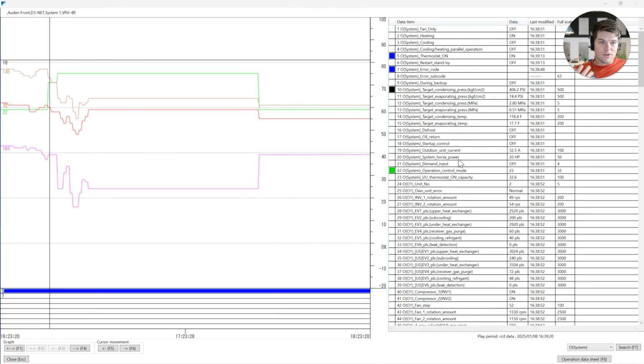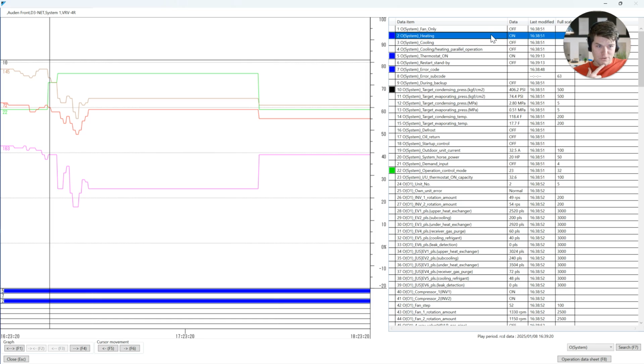Why is defrost important? Without defrost, we have ice coils all over the world and no one gets heating capacity and the heat pump movement is over. It's dead. Right? Defrost is important. This is heating before defrost, which means the system knows that it's about to go into defrost. And guess what? If you didn't know that, how are you going to tell that from on-off control? You're not. That's the answer, right?